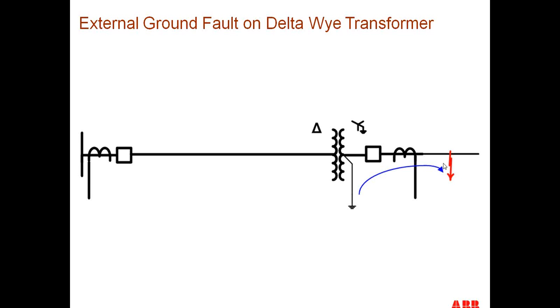When this occurs, as we know from transformer protection, this would normally cause a misoperation of our transformer differential, and in this case, line current differential relay. But just as we did in our modern microprocessor transformer differential relays, we can put in a zero sequence trap on this Y winding and this Y termination here, so that we block, or rather discard, any zero sequence current flowing through this CT, so that we don't operate for an external ground fault.